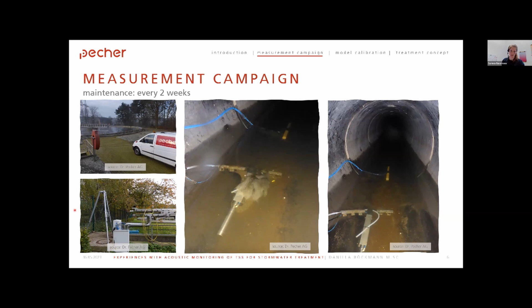For the maintenance, we drove to the measuring site every 2 weeks. And the 2 weeks rhythm was especially important for the cleaning of the optical probe, to make sure that the measurement slot was not blocked by anything. As you can see, sediment and paper or something accumulates. On the contrary, the acoustic sensor didn't get blocked so easily and needed less maintenance.